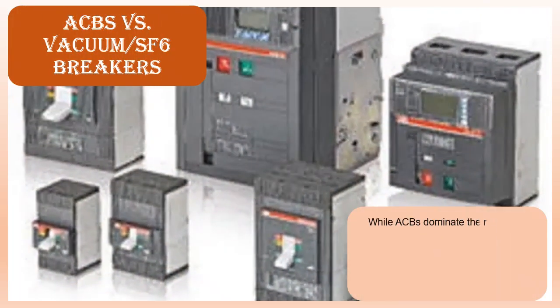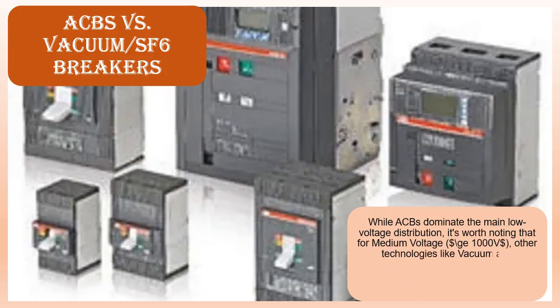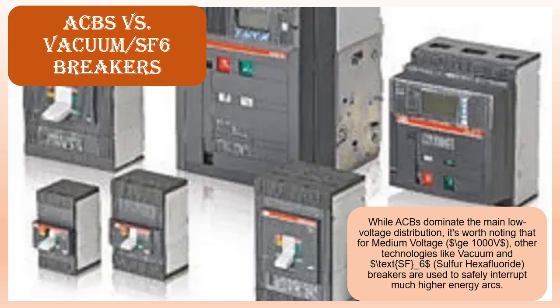ACBs versus vacuum and SF6 breakers. While ACBs dominate the main low-voltage distribution, it's worth noting that for medium voltage, above 1000 V, other technologies like vacuum and SF6, sulfur hexafluoride, breakers are used to safely interrupt much higher energy arcs.